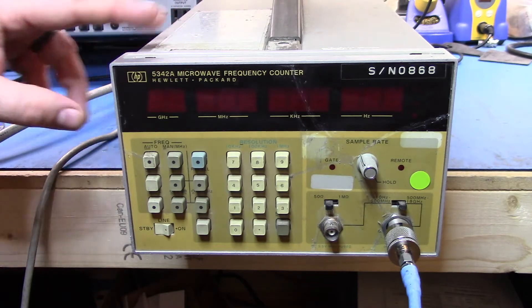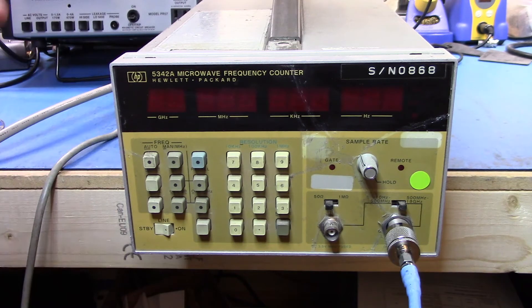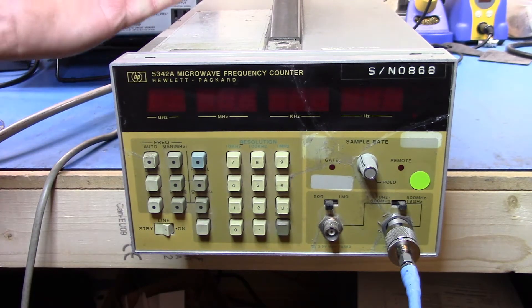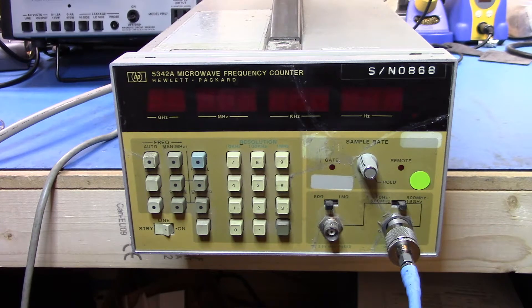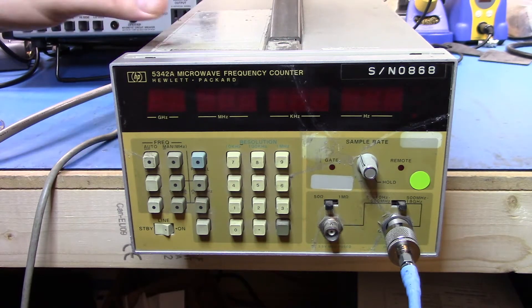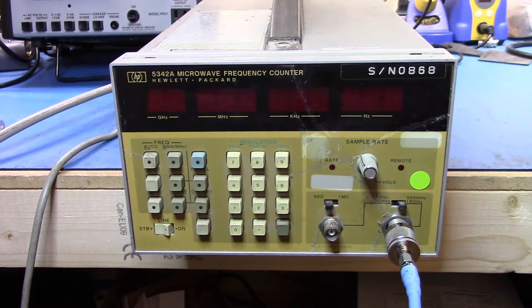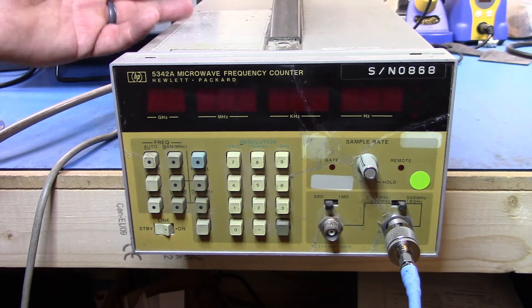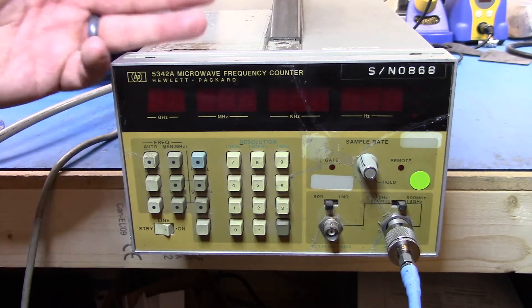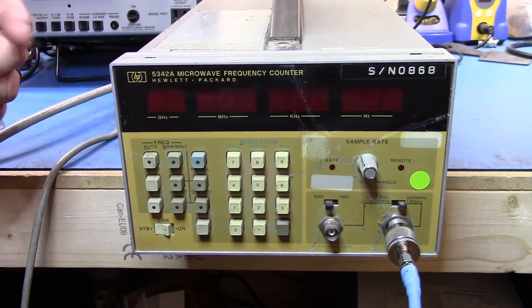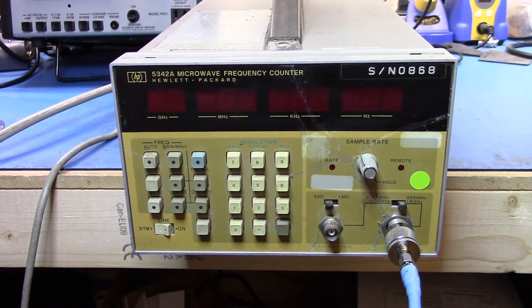So this counter is actually pretty cool. I've done a previous video on it, but this one here is basically a 10 hertz to 18 gigahertz counter, and it uses a unique method called heterodyne harmonic counting. And what that basically is, is it takes the heterodyne part where it will take a local oscillator and mix it with the incoming frequency, and then from there, it'll be able to send that resultant IF off to a counter to be counted.